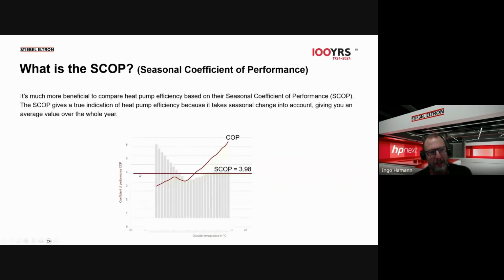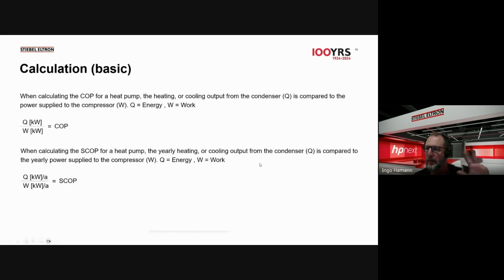You see here, the COP is going up, but over the whole year, the SCOP might not be a 5 or a 6, it might be only a 3.9 or a 4 point or whatever. Simple formulas, I don't want to stress you too much in the afternoon. You just have the free energy from the environment and what you need to put in as work, like kilowatts or kilowatt hours or kilowatt per annum, and then you get your COP. That's pretty easy, but if you don't know it, you might buy a heat pump with a COP of 5, but at the end, it gives you only an SCOP of 2 or 3.